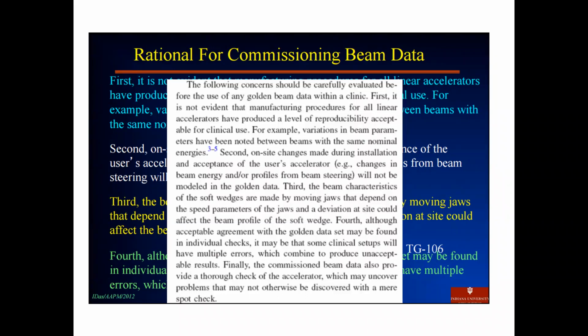Yes, we can have golden beam data, but sometimes the golden beam data and our beam data fall in an acceptable window range. Because of the specification of the machine and other resources, we may not be able to achieve or carry it for long. So it's good to have a machine commissioned. Certainly, if you have two sister machines in your institute, you can commission one machine, then compare the second machine with your data, and your first machine data will act as the golden beam data for your second linear accelerator.